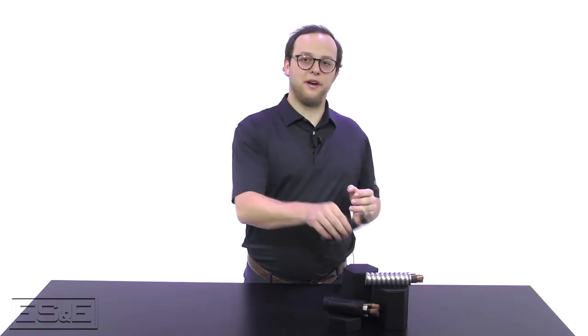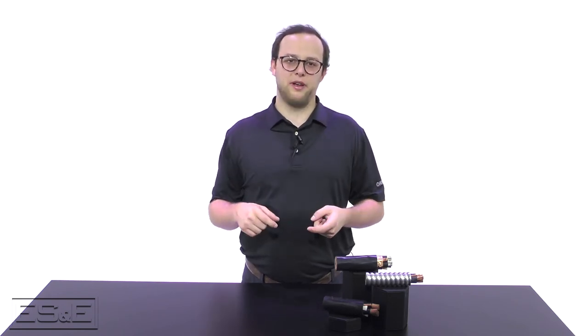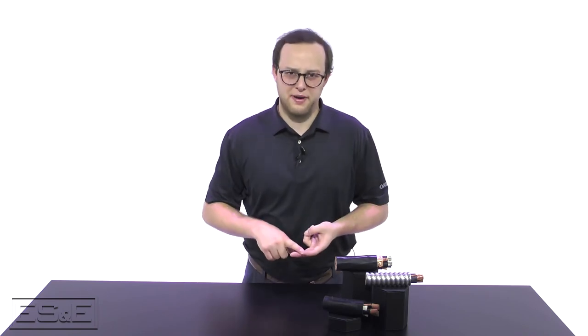Now that you know a little bit about VFD and where to use it, you might be wondering how to choose the right Belden VFD cable. The neat thing is Belden actually offers a tool that allows you to choose a cable based on motor voltage, motor horsepower, ambient temperature, temperature limit, and length of cable run — and it's called the VFD cable selector. We're going to walk you through a quick demonstration on how to use it now.